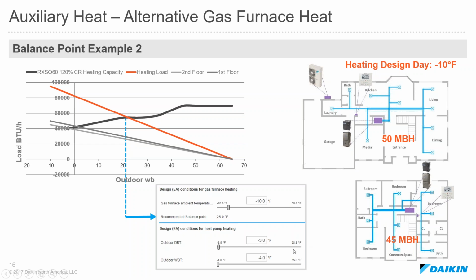Now it's important, in this case, to assign the correct design day temperature for your gas furnace, because the heating load is being pulled from the gas furnace, and that's how it's drawing this heating load line. So if we were to put -3 in here for that, it's going to change the slope of this line and then change that balance point. So you want to make sure your heating load and the temperature at which that heating load occurs match up within the selection tool.